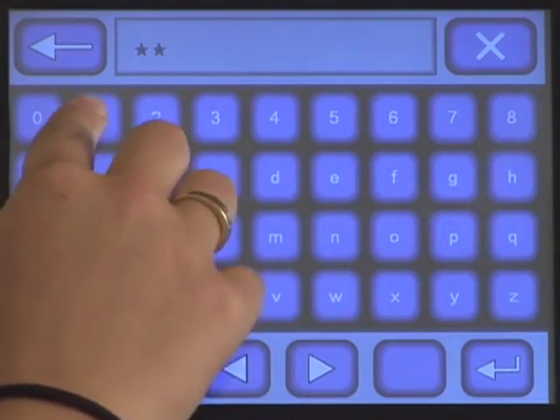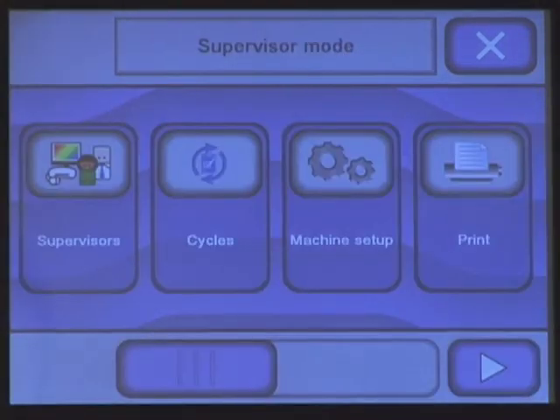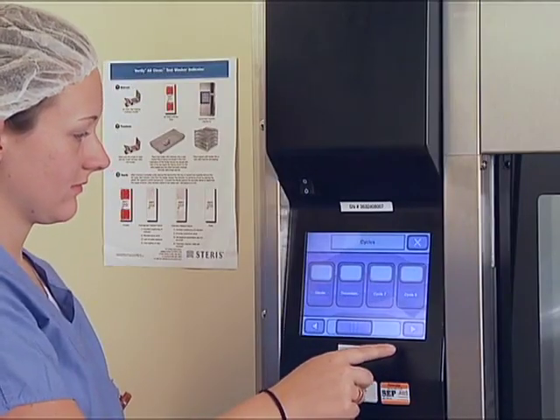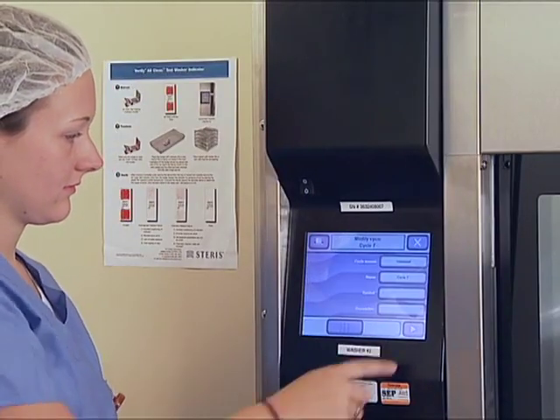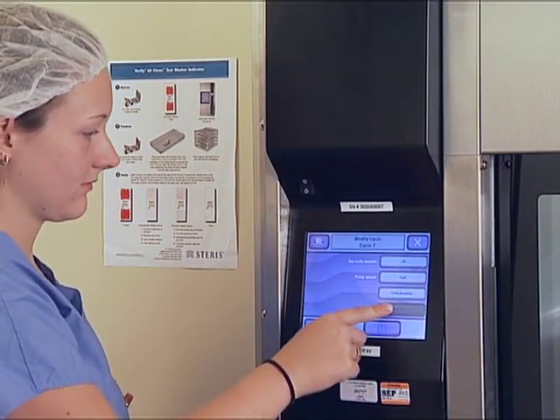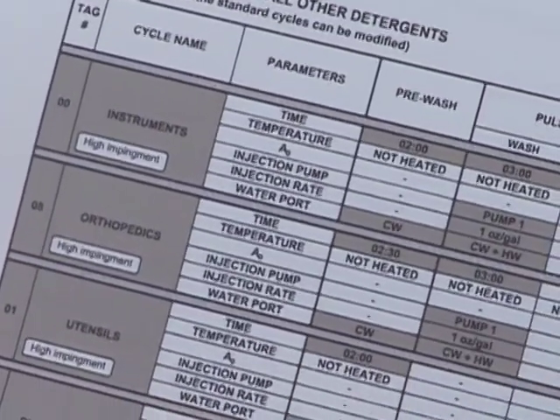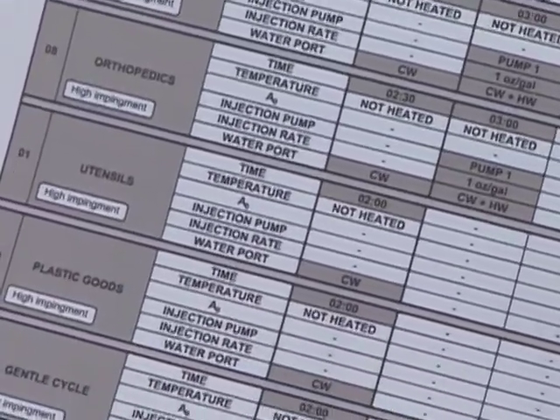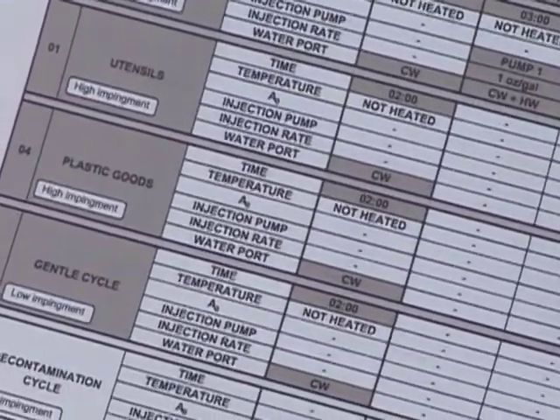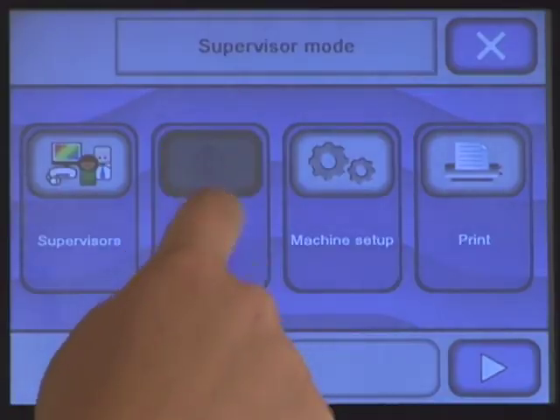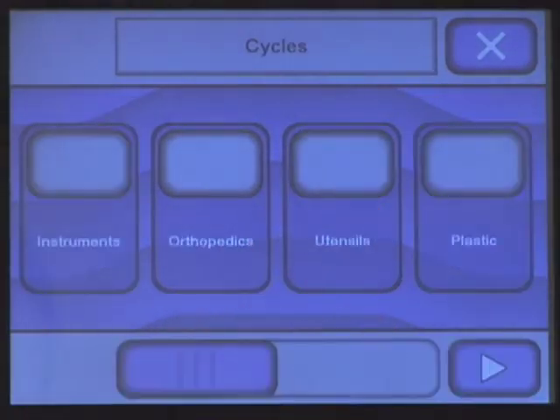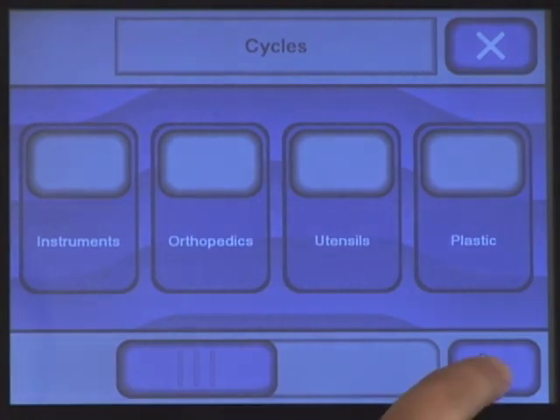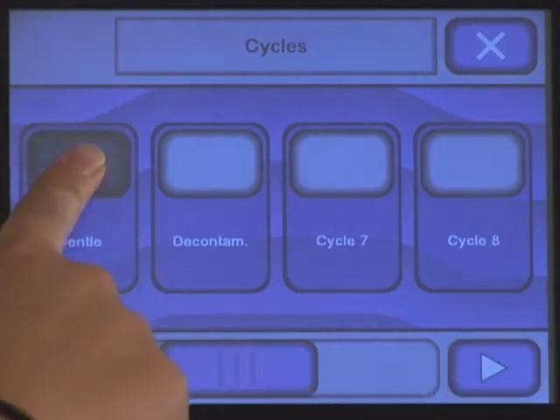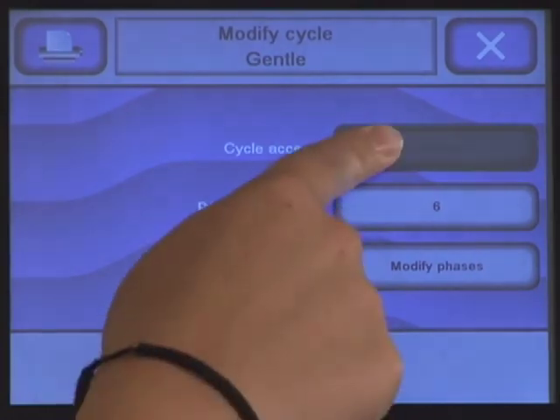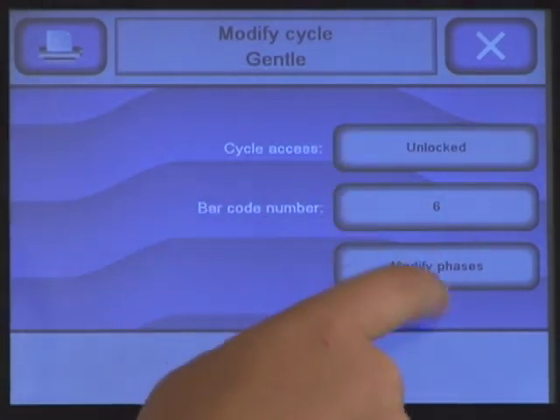Type in your password and press Enter. The PC control screen is now in supervisor mode. From here, you can either modify a pre-programmed cycle or customize a new one. Refer to Section 5 in your Vision Single Chamber Washer Operator Manual for details on what attributes can be modified and what ranges are allowed. To modify a cycle, press Cycles. Then Modify Cycle, and use the arrow buttons to navigate to the cycle you want to modify. Here you can lock or unlock a cycle, change a barcode number, or modify a phase.